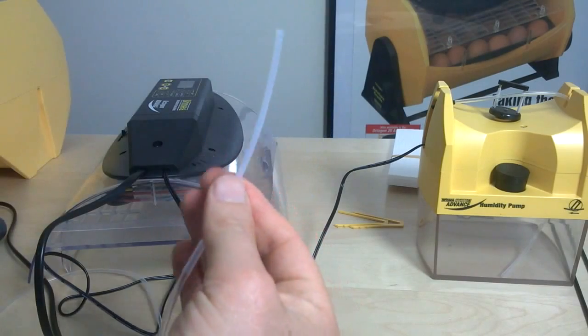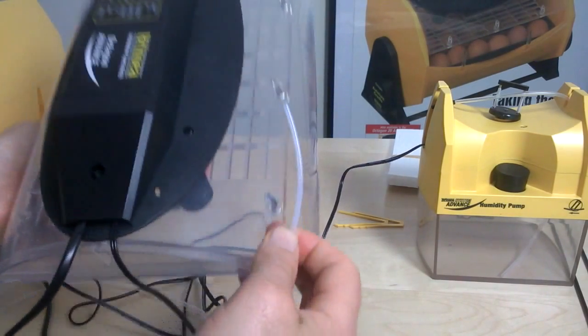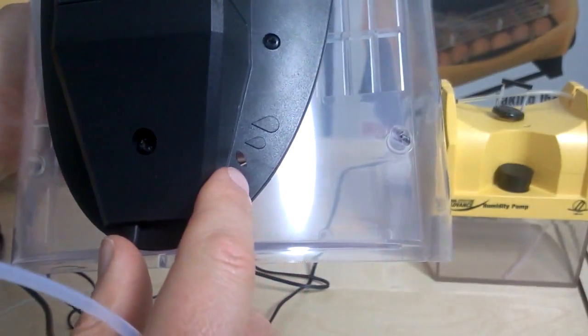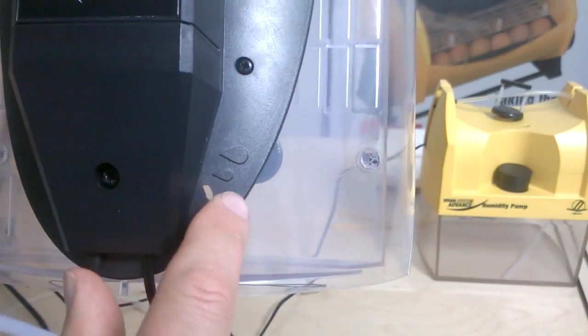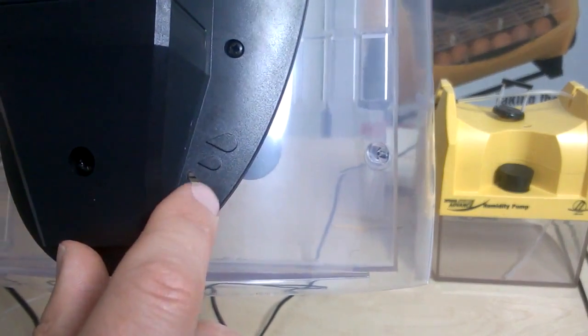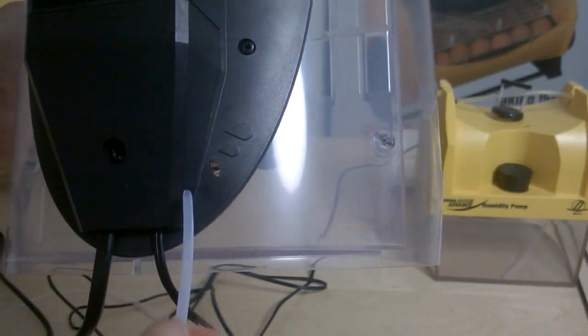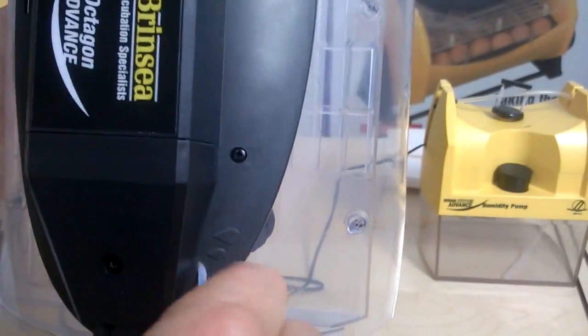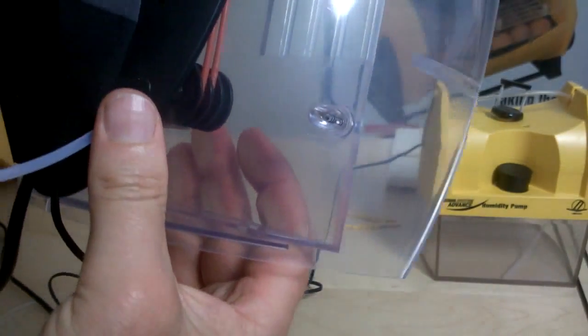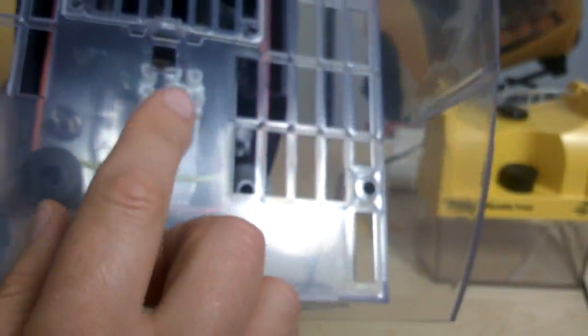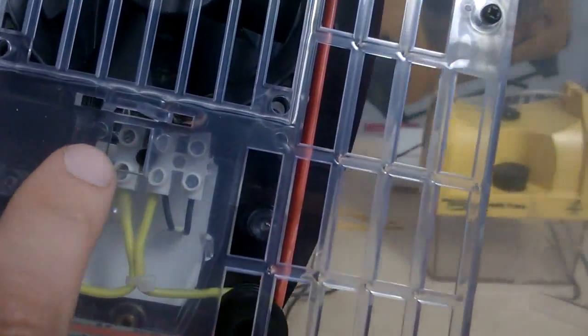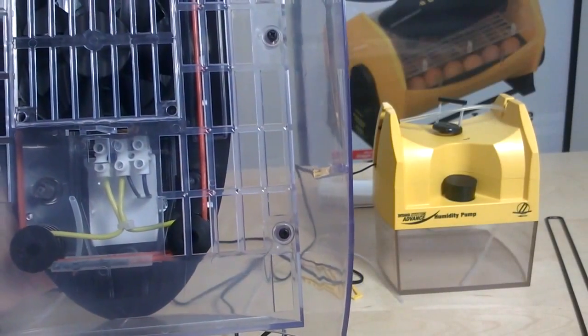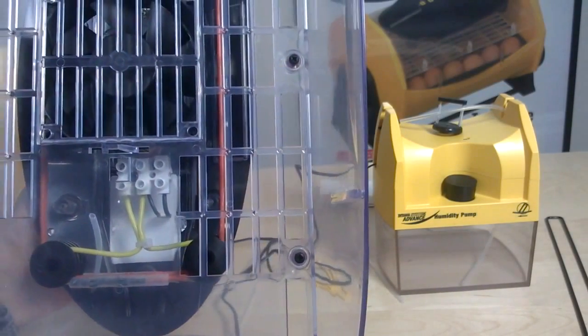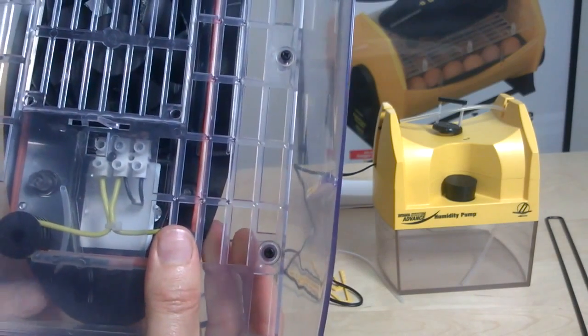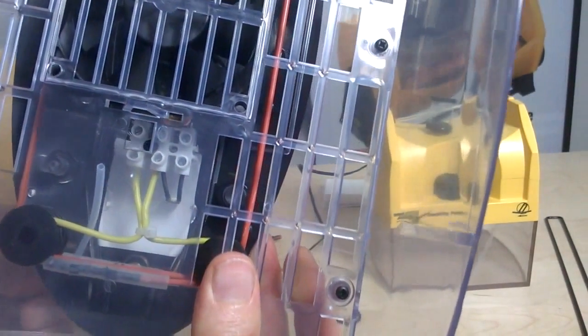Right, so what we're going to do is thread this through a little hole in the lid of the Octagon 20 for the humidity pump, and you can see that the hole is there, and there's a couple of water droplet signs which tell you that this is the right hole to thread our rigid tubing through. So we're going to thread that through the top of the lid, but we're also going to thread it through the little square hole that appears here as well. So I've got to thread the tubing up into here. It's going to be tricky. I don't know if you can see this. I've got the tubing coming through here.